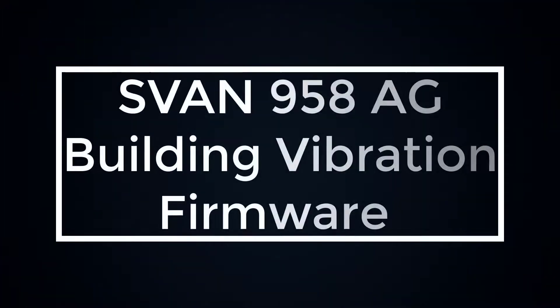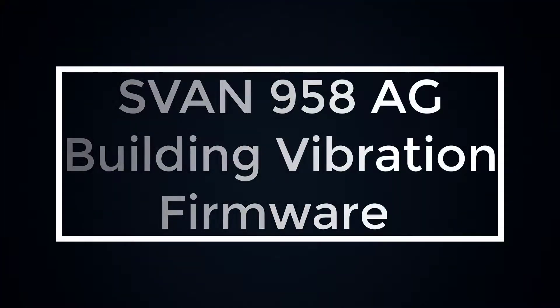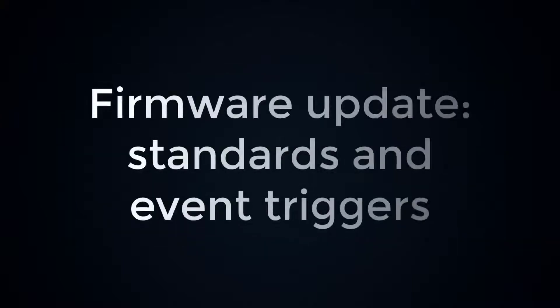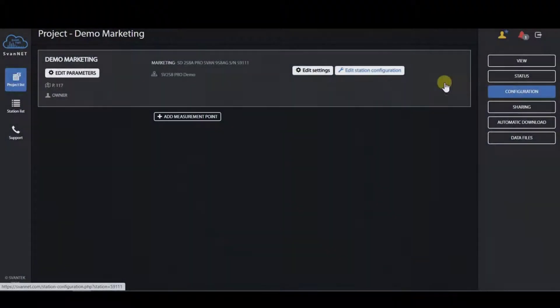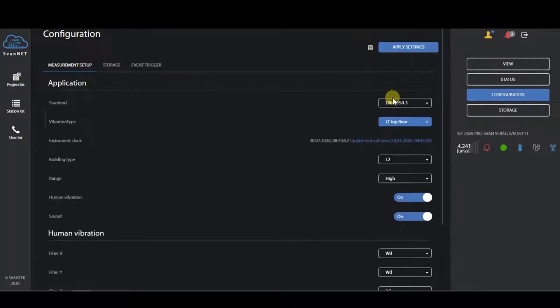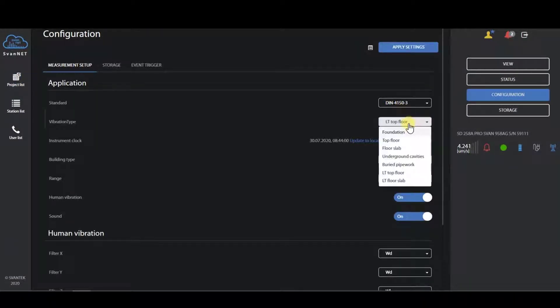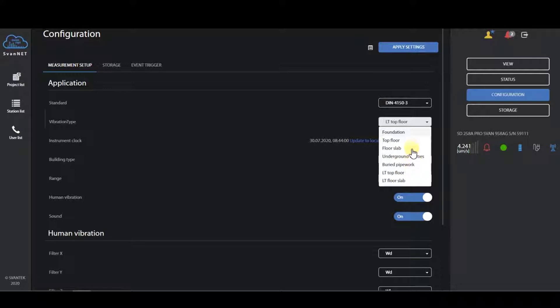In this video, we will show you the latest update that we have implemented with Svan 958-AG building vibration firmware. Together with updated DIN 4150-3, we have added the possibility to select various types of structures.